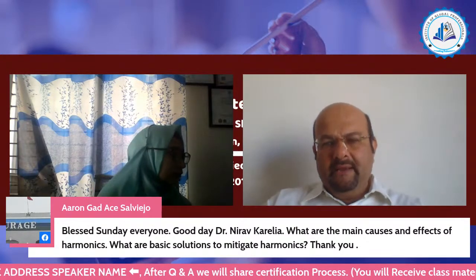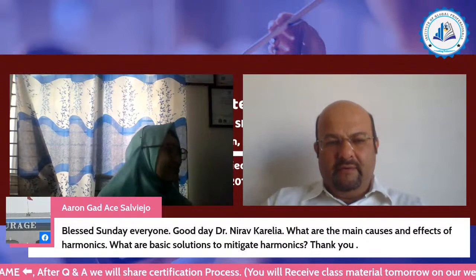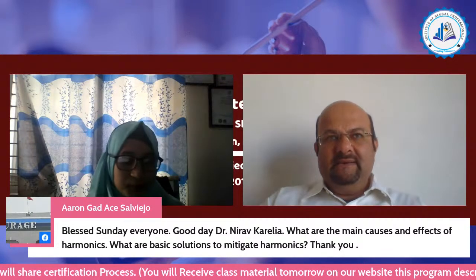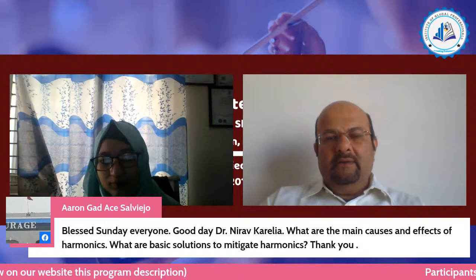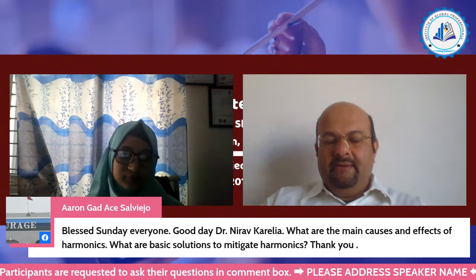The effects of harmonics I already enumerated. There are many effects, but the major one is that higher harmonics, that is higher frequency, causes more iron losses in the equipment. Due to that, temperature rises more than the rated rise. This causes insulation to die down early, the life expectancy of insulation reduces drastically, and hence the equipment fails earlier than it should.